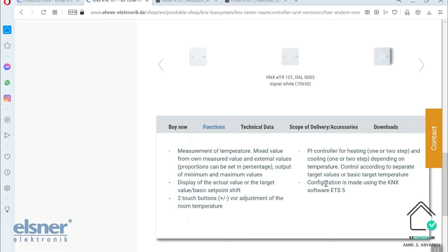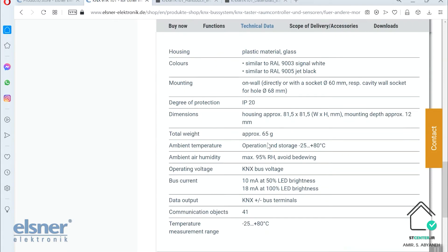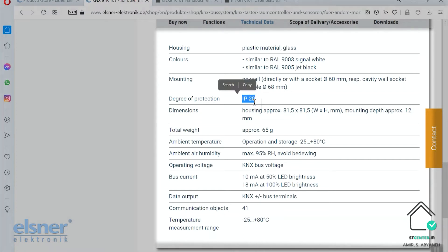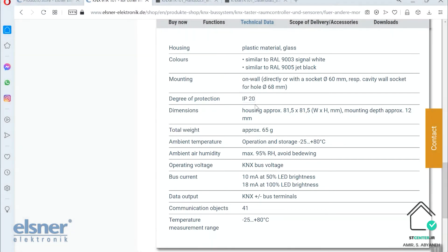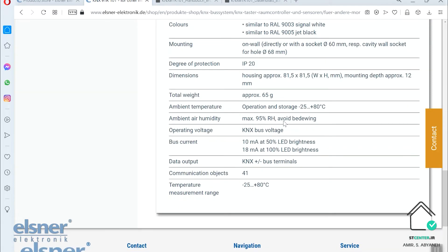It is configured in ETS of course. In the technical data you can see the surface is glass and the back is plastic. The environmental IP is 20 so you can only use it as indoor devices. The mounting is really simple. You can use the regular European standard for it. It is a little bit low weight, 65 grams only. You can use it in an environment between minus 25 to plus 80 with maximum 95 percent humidity. So it is quite a durable one.